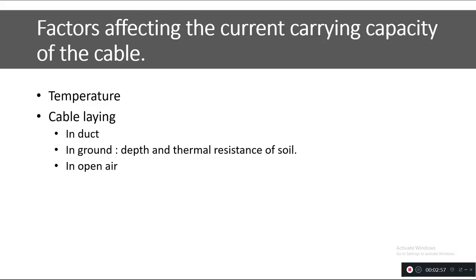For open air applications, you need to consider the atmospheric temperature as well as other factors. The first is the distance between the cables. Whenever you lay two cables beside each other, the current carrying capacity decreases due to mutual inductance and other factors. You need to refer to the cable manufacturer's datasheet for the recommended spacing between cables to minimize that effect.